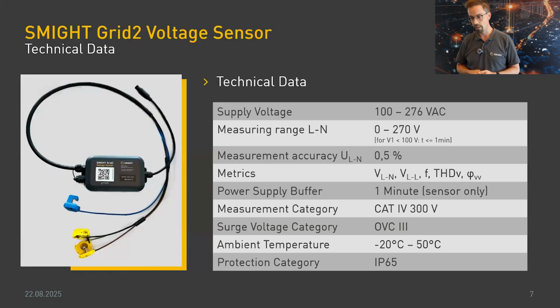I've got the key technical data up on the slide. I'm not going to go through all of it, but a couple of points are worth mentioning. First is the measurement accuracy, which is at 0.5%. That's different from our standard system at 3%, because here we're measuring voltage for the purpose of measuring voltage, not for phase angle calculations, so it's much more important to have that higher degree of accuracy.